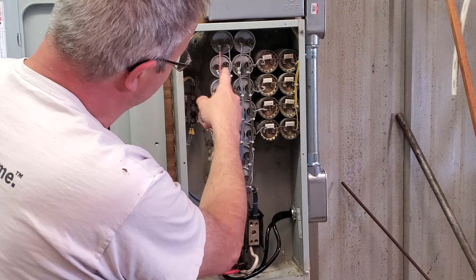And that feeds the relay box. Let me open this up and show it to you. Now the power is off. Incoming power feeds the left and center terminal block - these are your L1 and L2, and then the ghost leg is the white line coming out here. These are the balancing caps for the run circuit, and these are the starting caps with the bleed down resistors for the starting circuit. It has an adjustable time delay and a contactor that will momentarily energize this ghost leg until the motor starts generating voltage in that third winding. Then this will sense that and cut those starter capacitors out of the circuit, leaving the running capacitors connected for running.